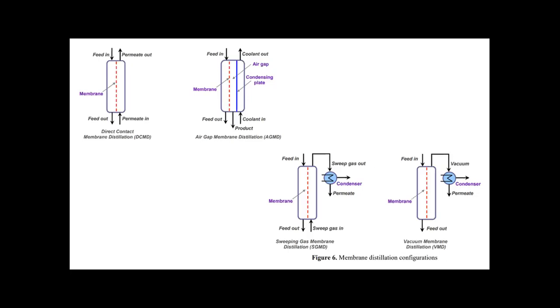In DCMD, various membrane types can be used: flat sheet membranes, spiral wound, capillaries, or hollow fiber membranes. A variety of membranes are available and depending on the requirement, a specific type must be selected. The second membrane distillation type is AGMD — Air Gap Membrane Distillation. An air gap is added between the membrane and the condensing surface. In DCMD, heat loss by conduction was the main drawback; in AGMD, the air gap acts as an insulator to decrease those conduction heat losses.